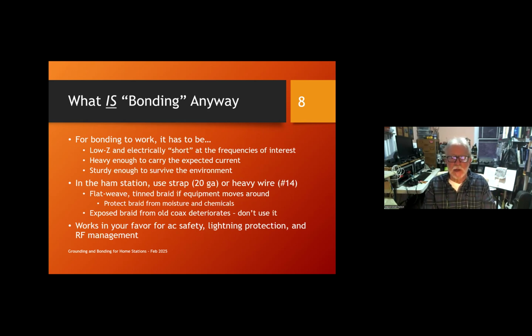Well, what makes bonding work? Well, it has to be low impedance. You don't want a lot of impedance between point A and point B. If you have impedance and you have a voltage difference, well, you're going to have current, and that's going to create a current drop. So low impedance is good at whatever frequency we're talking about, 60 hertz or microwaves. And it has to be electrically short. And that means much less than a 20th of a wavelength is my general rule of thumb.